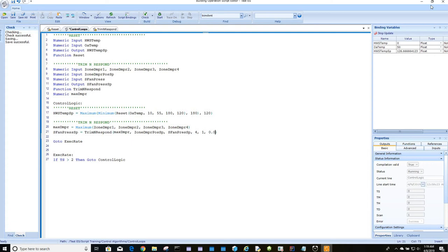Our trim, so we can see it react fast, is going to be 0.05, but truthfully, and you'll see why when we debug, you want this value small, because you don't want these changes to occur fast. I would always set this value to no more than 0.02, but typically as low as 0.0005.